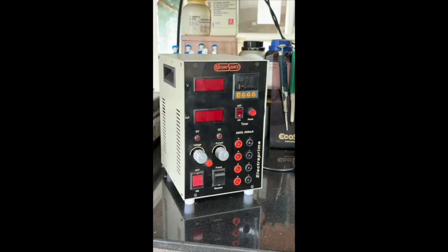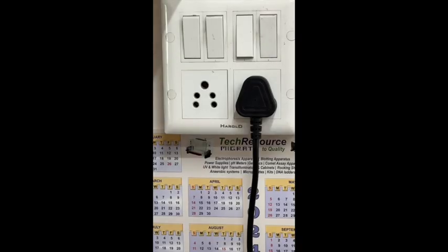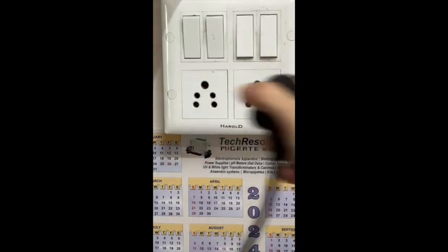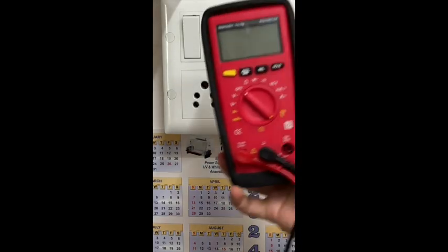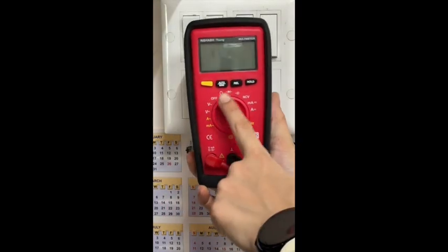Indication 1. The power supply does not switch on. Here, there is no light on any of the indicators. The cause is probably that the mains supply is not available to the power supply. The suggested action is to check the 230 volts mains supply. To do this, you can use a multimeter set to read alternating voltage.